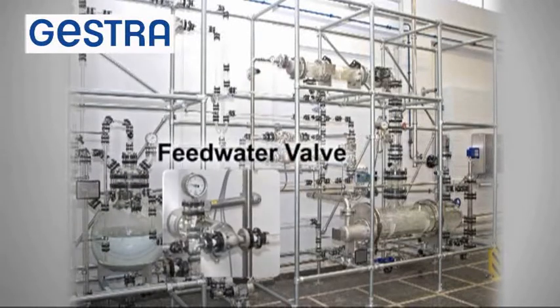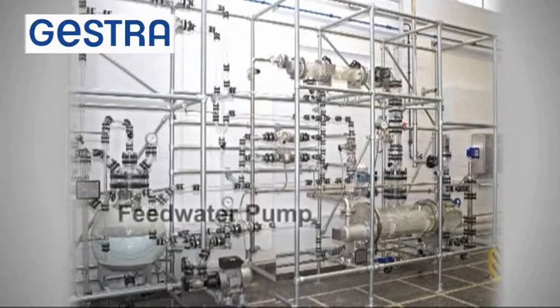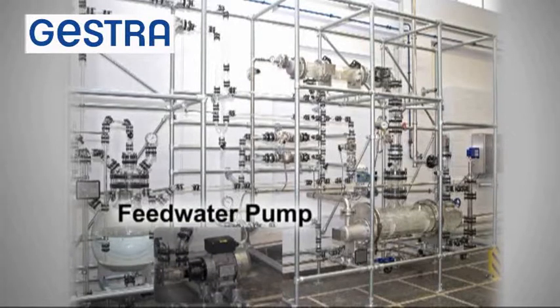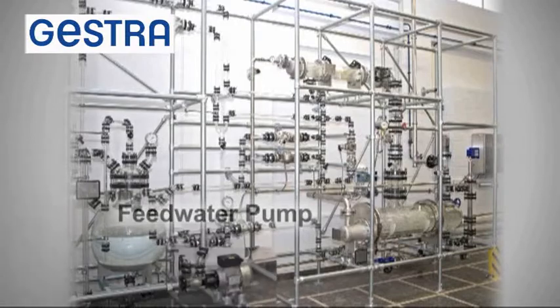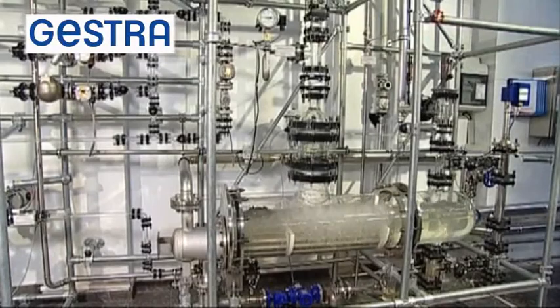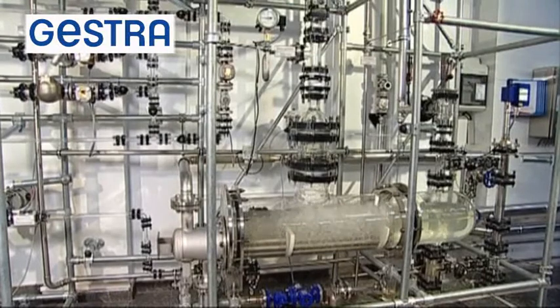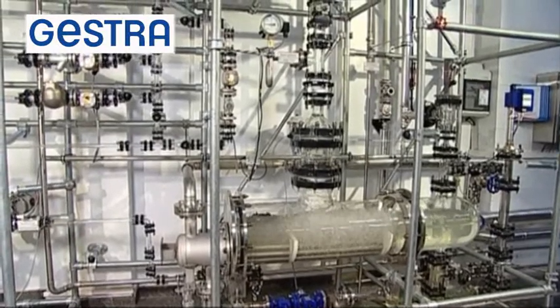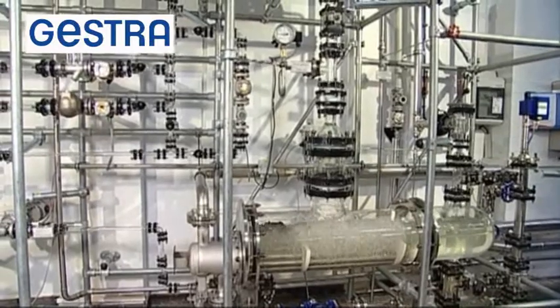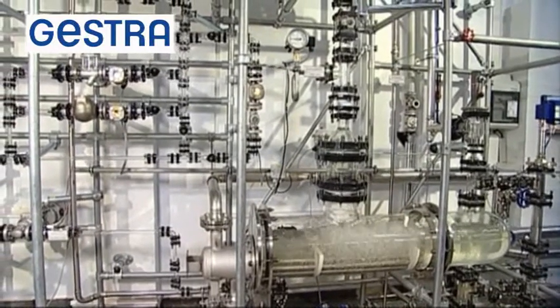Thermodynamic processes taking place in the generation of steam, as well as during condensation, condensate discharge, and the origination of the water hammer effect are shown in a way that's easy to understand. This video looks at condensate discharge by means of various kinds of steam traps, as demonstrated in the glass steam system of GESTRA AG, Bremen.